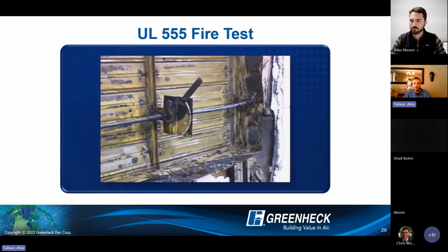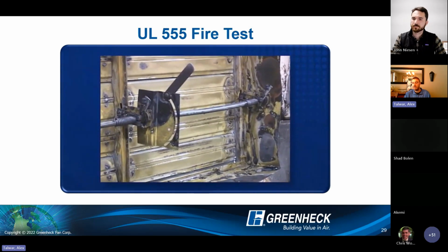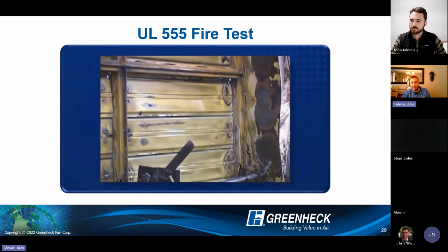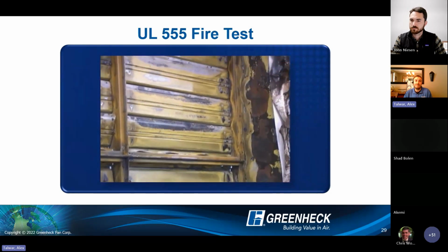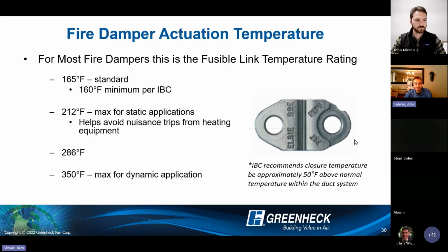And after absorbing all of that force and temperature and fire and water and all that stuff, now our UL witness will start taking measurements, and you are allowed 1/8 of an inch for a through opening for a tolerance. So I mean, think of how big 1/8 of an inch is. We'll have a rod that's 1/8 of an inch in diameter, and our UL guy will be poking around the corners of the product and making sure he can't push that rod all the way through. So that is your tolerance for a through opening for passing these UL fire tests.